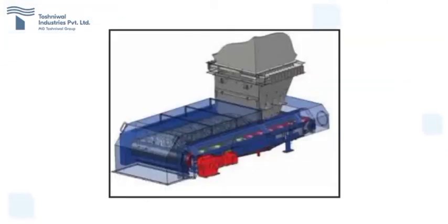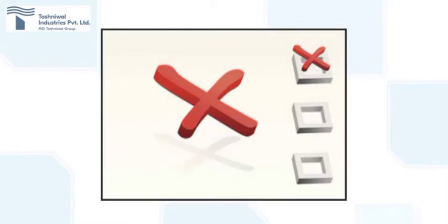The material fed in ball mills is generally measured with the help of weigh feeders placed in the inlet circuit of the material getting fed. But feeding without actual level measurement of ball mill can result in various problems like overfilling causing jamming, or underfilling resulting in low productivity, higher power consumption and breaking of balls and liners sometimes.